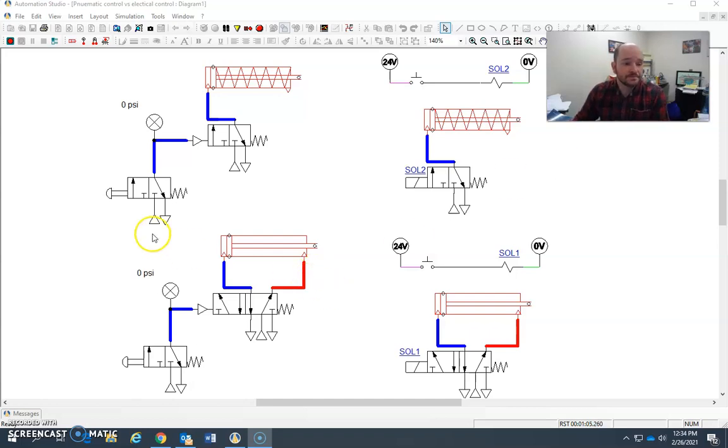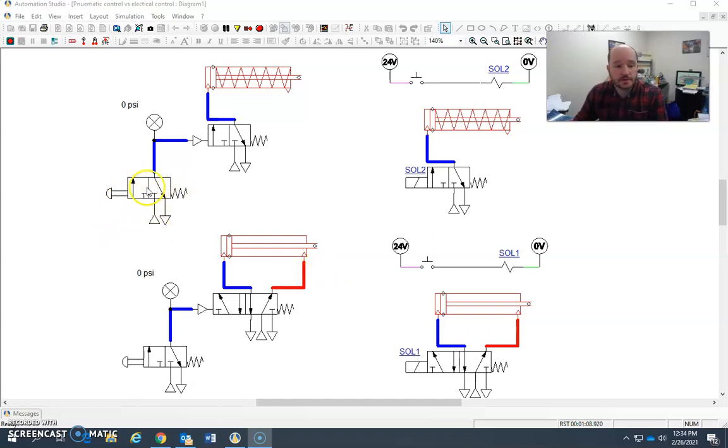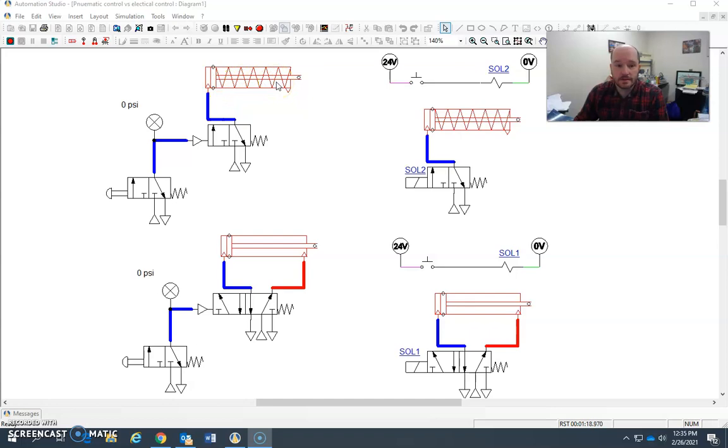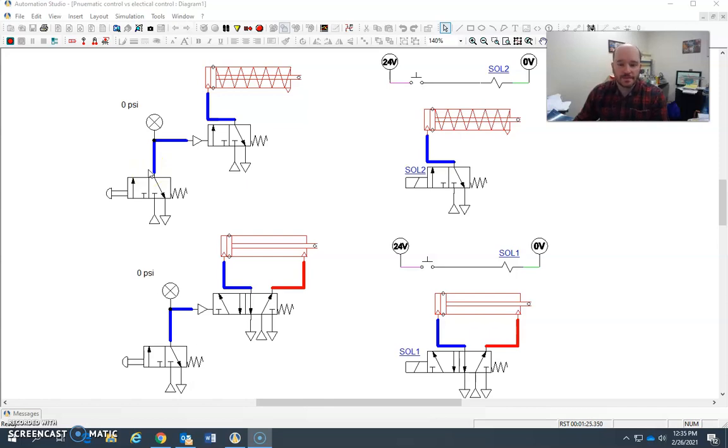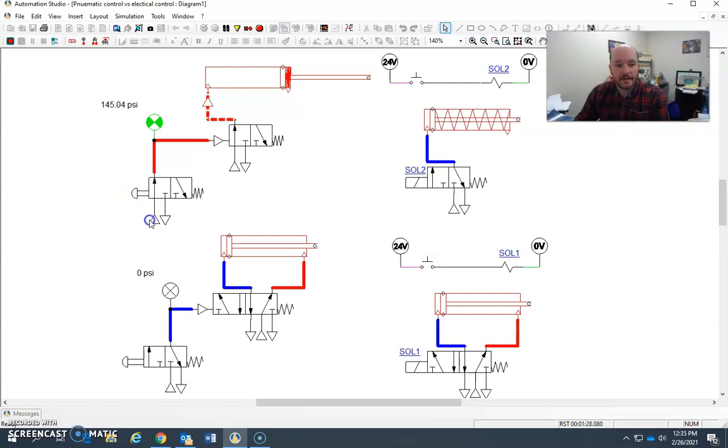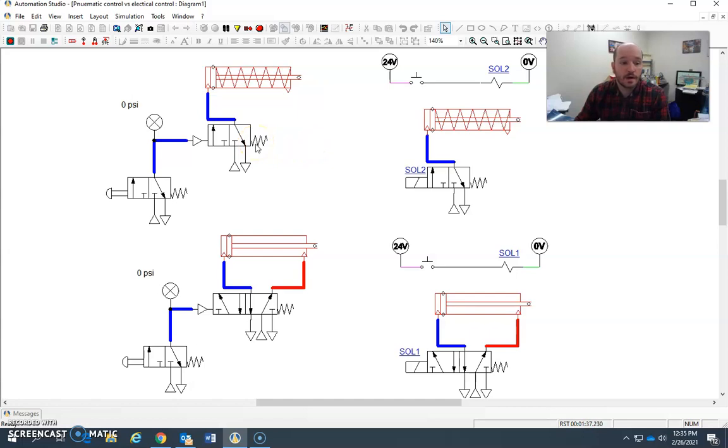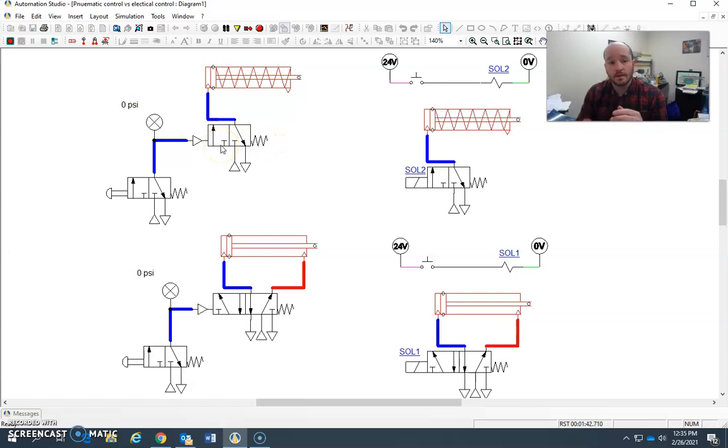Here I just have a real basic circuit. I have a 3-2 directional control valve push button controlling a 3-2 air actuated push button. Now the advantage of this is this directional control valve can be very close to the single acting cylinder. This can be located away from the cylinder at a control panel or something like that. So I can come here and activate it. Air will come up, reposition the 3-2 into an open position, and extend the cylinder. When I release the push button, the spring on the 3-2 external pneumatic control and directional control valve returns it.